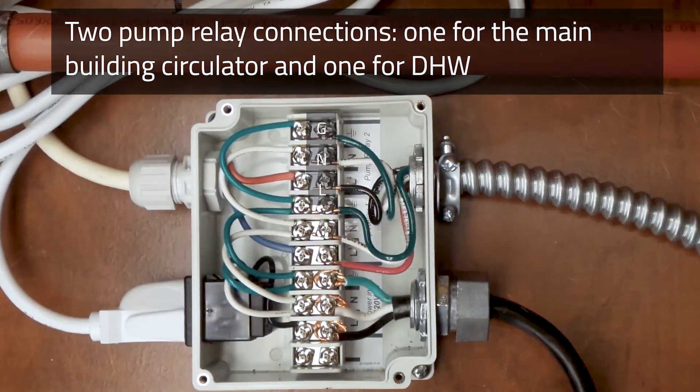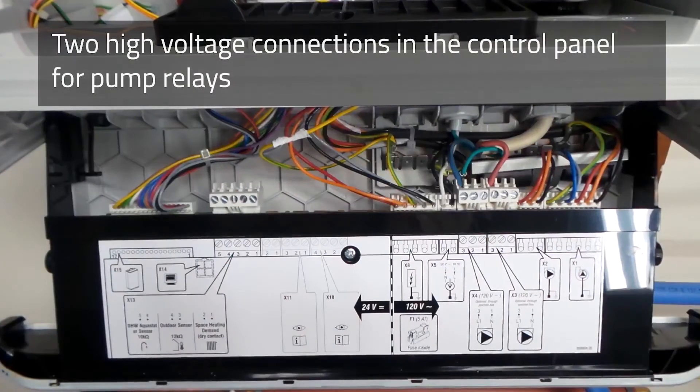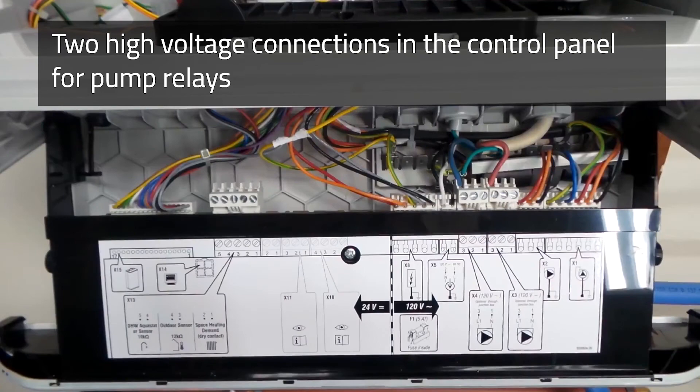As you can see, there are two pump relay connections here, allowing us one for the main circulator for the building, and the other for the DHW. Beyond that, we have the two high voltage connections that go down to our control panel for the pump relays.